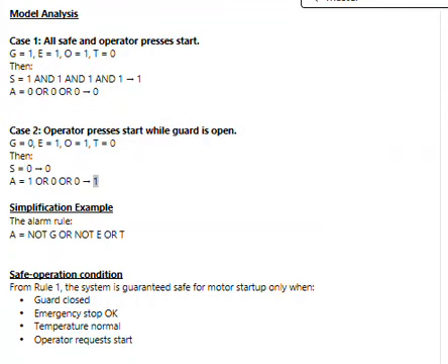The system effect of this conclusion is that we could say the motor is blocked and the alarm is active. Again, this behavior is what we would want the control to dictate in this particular condition: a blocked motor while we have an operator requesting a start.